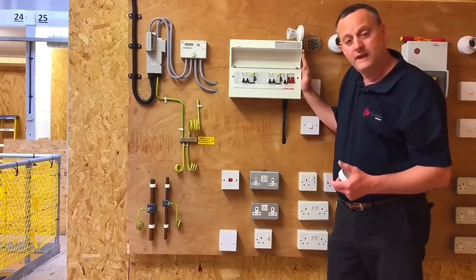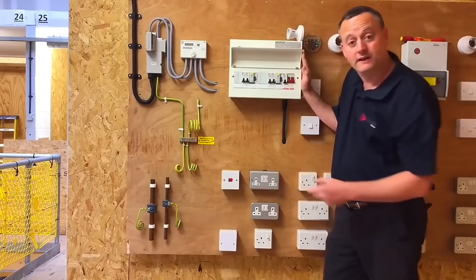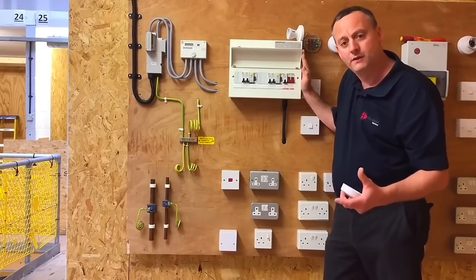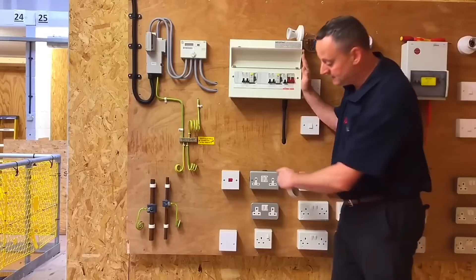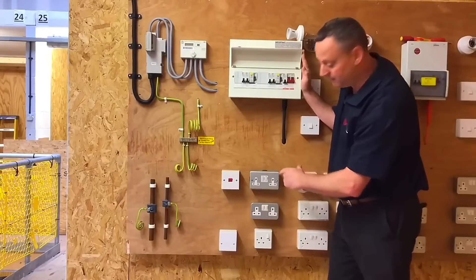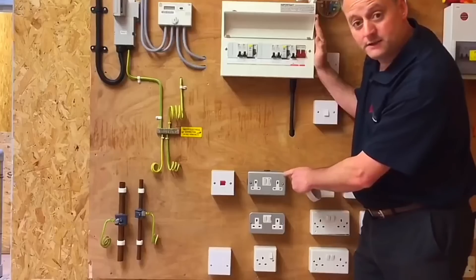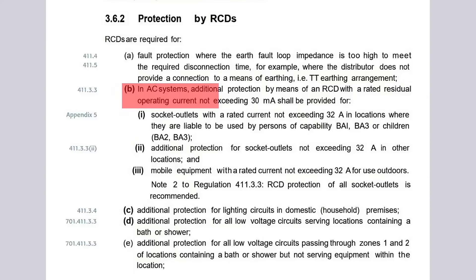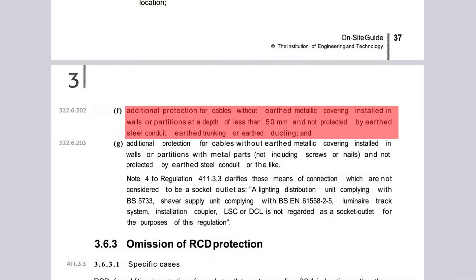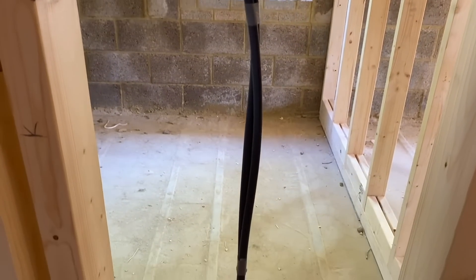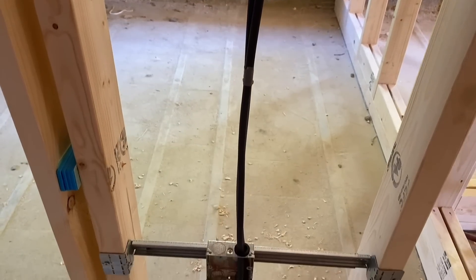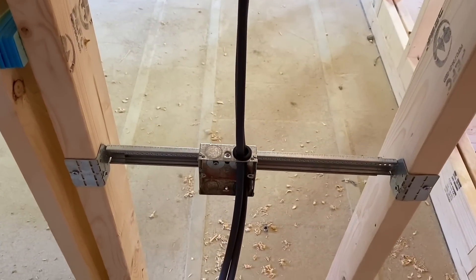Additional protection is required for socket outlets — 13 amp socket outlets. Currently in the regulations it says socket outlets up to 32 amps; it isn't the rated value of the breaker, it's the rated value of the socket outlet itself. These are 13 amp socket outlets. All socket outlets in a domestic dwelling are going to require additional protection by an RCD rated at 30 milliamps. Other additional protection will be required where cables are running in stud walls. If you've got lighting circuits, cooker circuits etc. running in stud walls with no further protection, additional protection would be required. If you're not burying cables in the wall at a depth of 50mm or greater, those circuits will need additional protection.